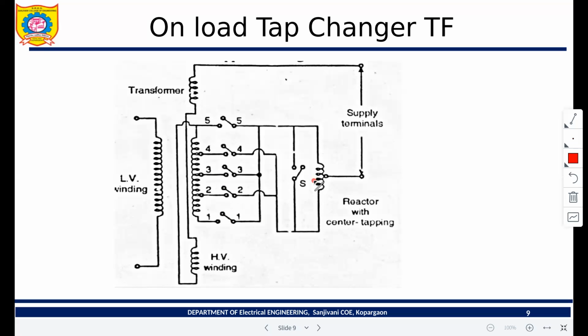Now, when you switch from 1 to 2, you can switch off 1. So under switching operation, this function can be done. Open the switch, from switch 1 close switch 2, then half of the current will flow through this reactor in the opposite direction. So there is no short circuit across the tappings. Then open switch 1. Are you getting it? Now, in the same way, open the switch, close switch 3, then half of the current will flow over here. Again close switch S1 and open switch 2. Like this, the function is operated.